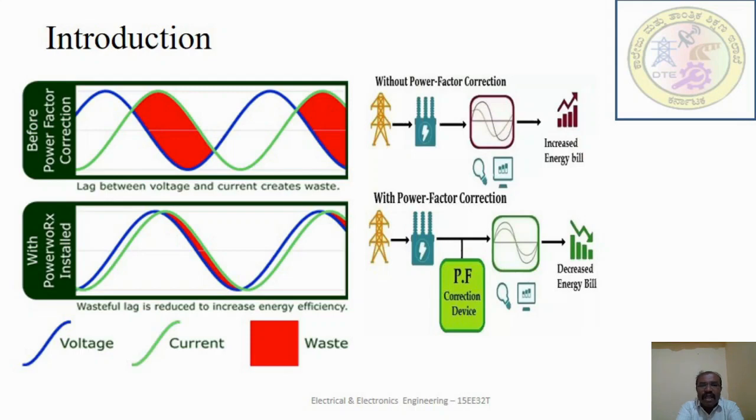A consumer has to pay electric charges for his maximum demand in kVA plus the units consumed. If the consumer improves the power factor, there will be a reduction in maximum kVA demand, and consequently annual savings in maximum demand charges. If they invest in power factor improvement equipment, there will be annual savings for the consumer because of maintaining the power factor at the proper value.